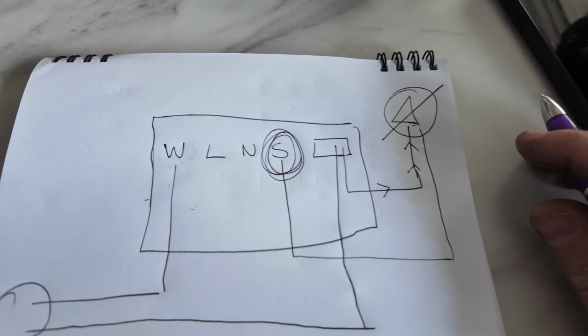It's a kill switch. So I hope doing that little diagram there has helped it make sense. You're just basically using your pump as a kill switch, so if it ever fails, it'll stop the unit. The last thing you want is condensate building up. So that's how you wire up them little pumps. They're dead easy, to be honest with you.